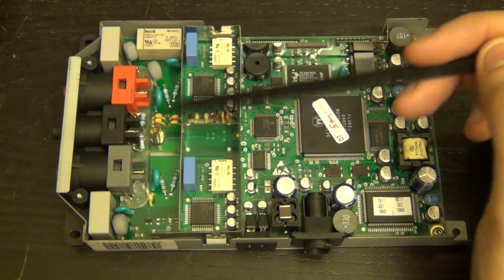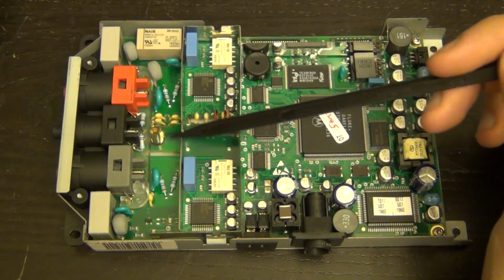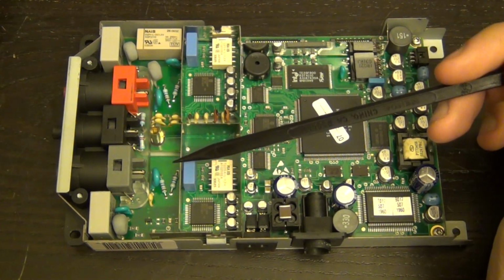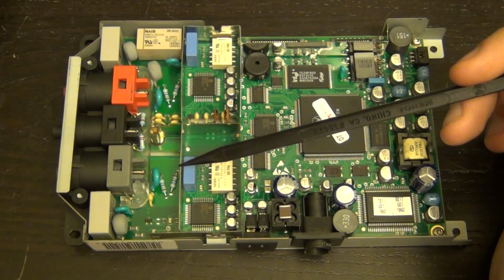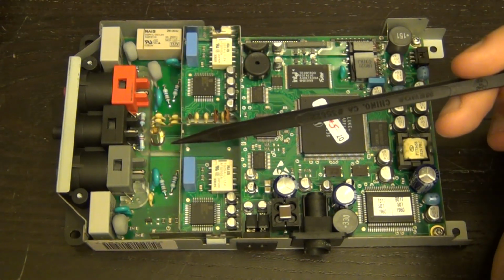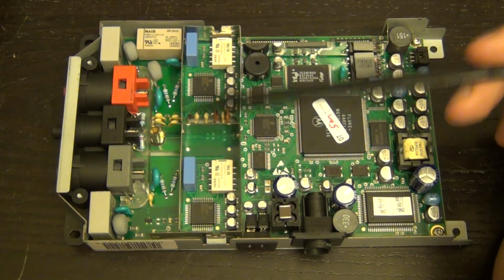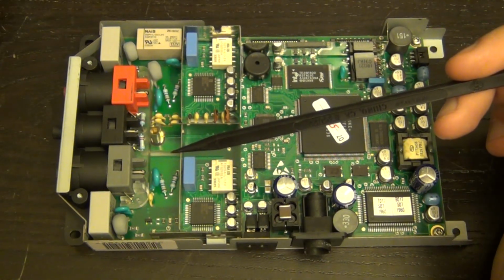You can see different capacitors, MOVs, resistors, and different gaps in the PCB to protect against high voltages arcing across it. Every input in this instrument is Cat3 600 volt rated, as expected, which is why there's so much protection circuitry in there.